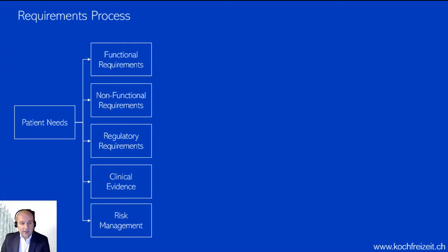to also have a look at the countries you want to launch in. So look at the FDA requirements, Australia's TGA, Europe's medical device regulation requirements, etc., and understand what you need to do to comply. You need to look at the clinical evidence you need. And again, there's an interrelation here between the regulatory rules and what you need to provide to meet those regulatory rules. And then the core of the product as well is the risk management. You need a risk management file and start identifying hazards and mitigating actions, which will cycle back into some of your requirements.